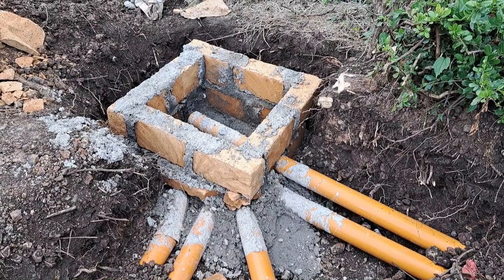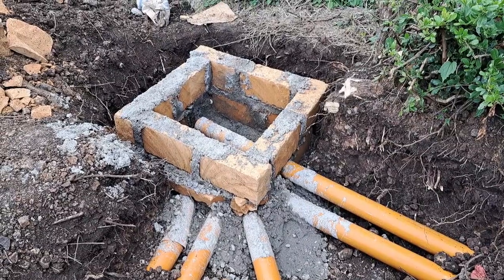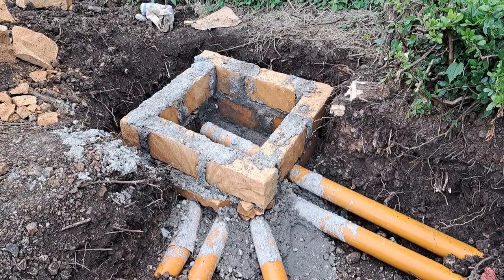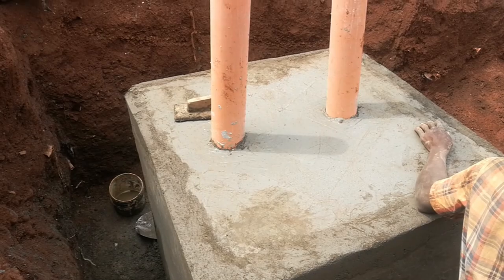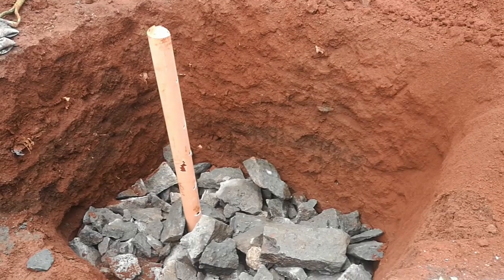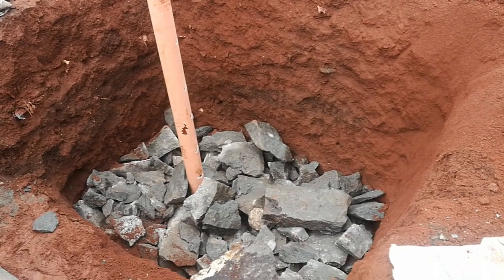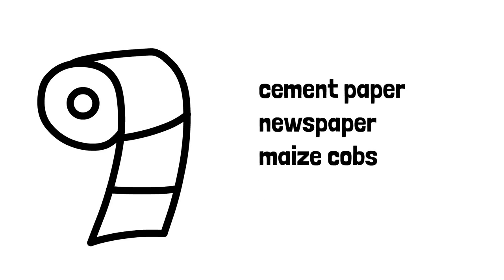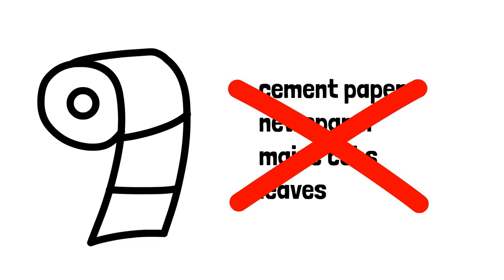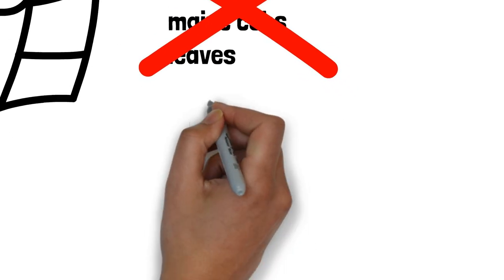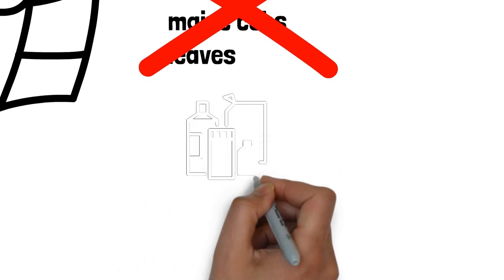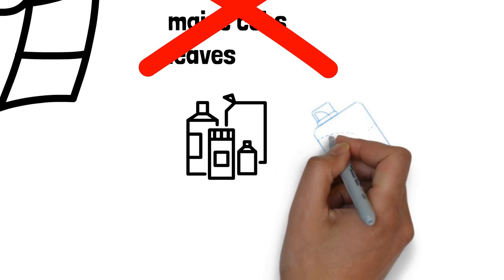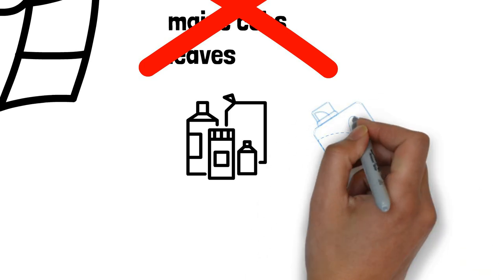Routine maintenance checks should be done yearly. Checks for blockages should be done for the manholes, the biodigester chamber, and the outlet pipe leading to the soak pit. In terms of use, the acceptable anal cleansing material is tissue paper. Other cleansing materials will make the solids inside the biodigester to fill up quickly as they won't be digested as easily by the organisms. Toilet cleaning chemicals like bleach or antiseptics should be added according to the instructions on the labels.